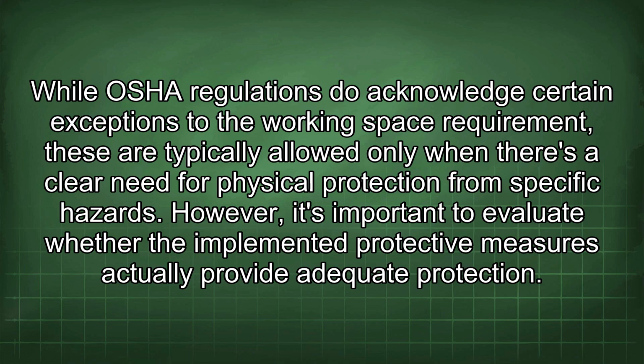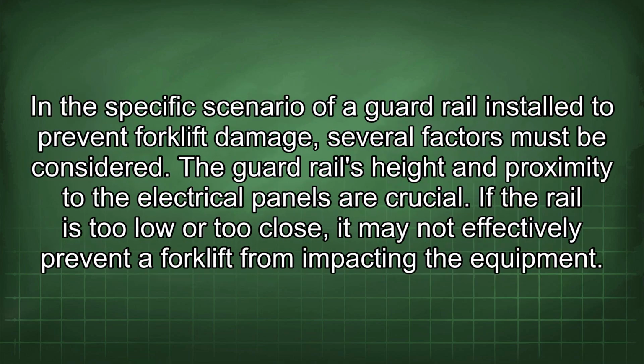While OSHA regulations do acknowledge certain exceptions to the working space requirement, these are typically allowed only when there's a clear need for physical protection from specific hazards. However, it's important to evaluate whether the implemented protective measures actually provide adequate protection. In the specific scenario of a guardrail installed to prevent forklift damage, several factors must be considered. The guardrail's height and proximity to the electrical panels are crucial. If the rail is too low or too close, it may not effectively prevent a forklift from impacting the equipment.